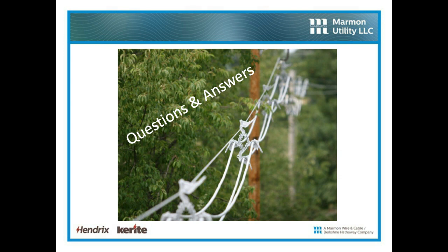Okay, great. Thank you. Next question, are there limitations with a severe ice load? There's no limitation on the system. There's certainly limitations on the poles. So when we're designing a system, whether we design that system here with PLS CAD, or we're working with the utility with one of their loading programs, basically they're designing it just like a bare wire line. They're going into their NESC regions or their CSA regions or whatever loading conditions they have, whether that's 0 degrees Fahrenheit and 3/4 of an inch ice and 60-mile-an-hour wind. We model the system and we see what safety factor we have in the pole. So again, there's no limitation on the system. The limitation is going to be on the pole, and that's why we take a look at the poles when we design these systems. And also, that goes into defining which messenger we use, the rated tensile strength of the messenger.